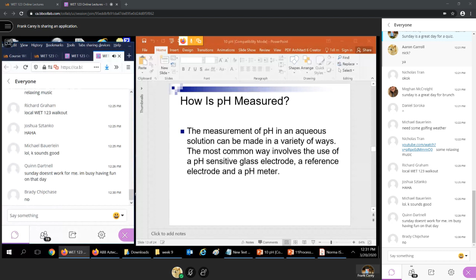an electrode that measures the concentration of hydrogen or hydroxyl ions in a solution that dissociate through a permeable glass bulb. So the holes in this glass bulb are small enough to allow hydrogen ions to pass through, and that will cause a reaction inside the solution, which creates a millivoltage. And this millivoltage is then compared to another reference electrode.